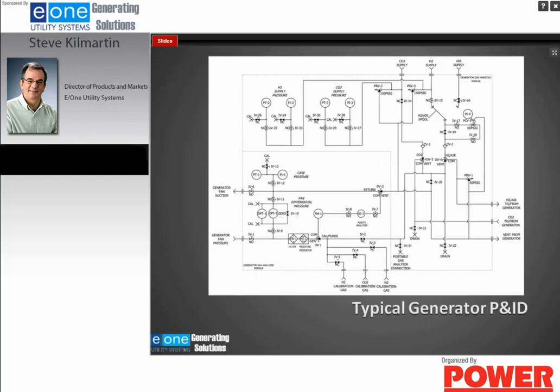This is a typical hydrogen P&ID for a generator. I'm going to point out a few components in here. In the lower middle of the page is the purity analyzer, and that's what we're going to be discussing. What I'd like you to know is where the sample for the purity analyzer comes from. Now, during normal operation, the sample will come from the generator fan pressure.